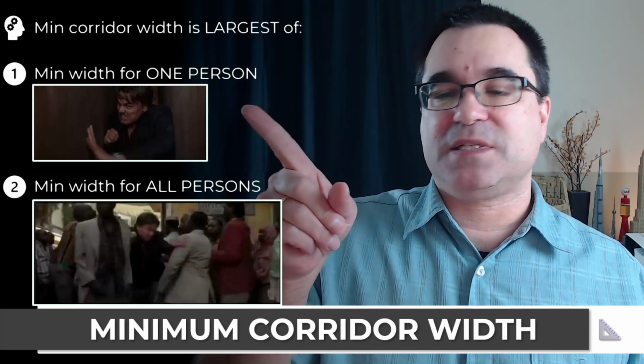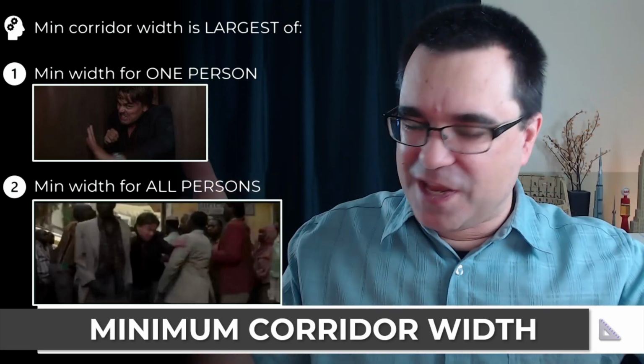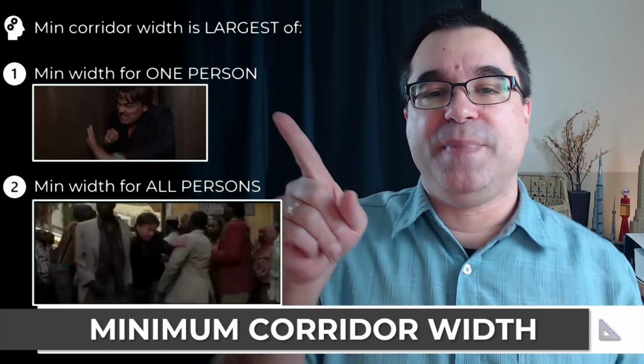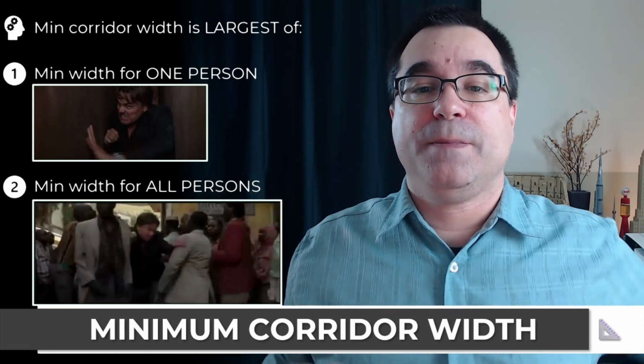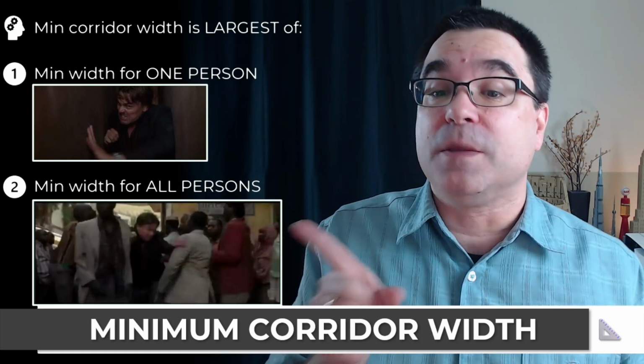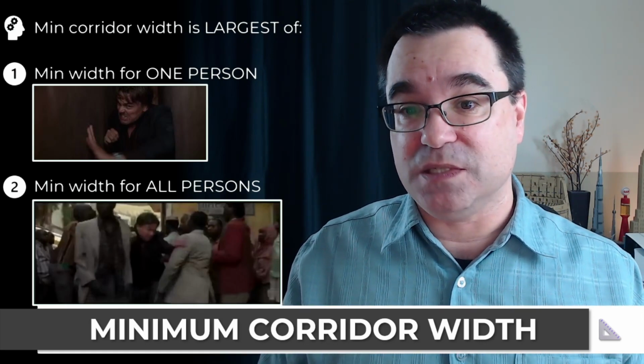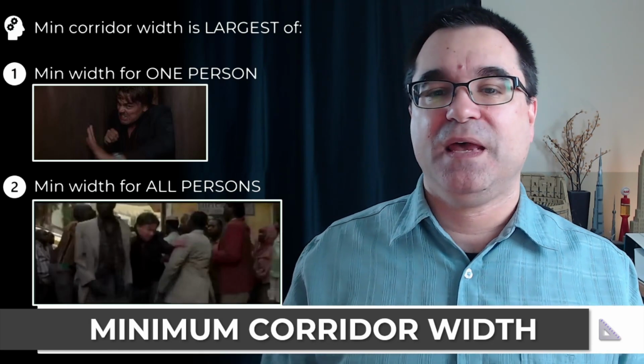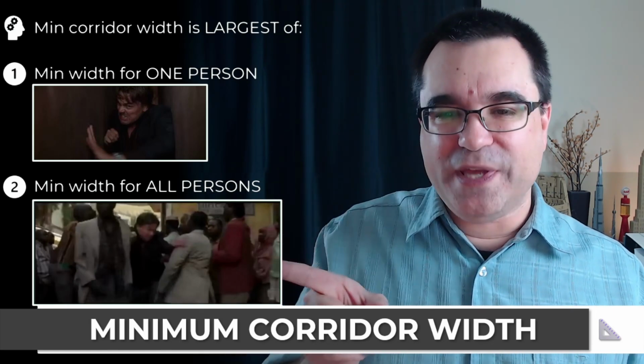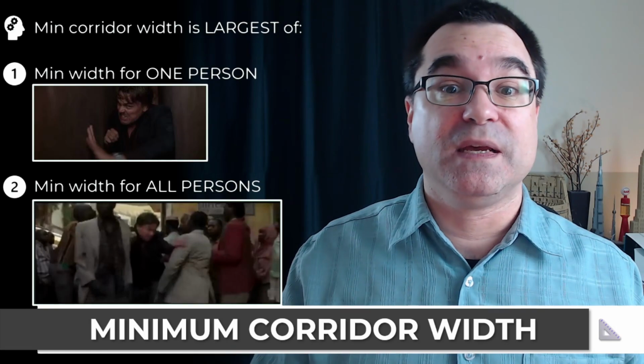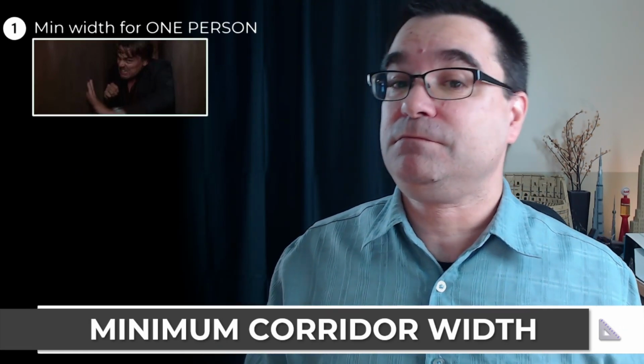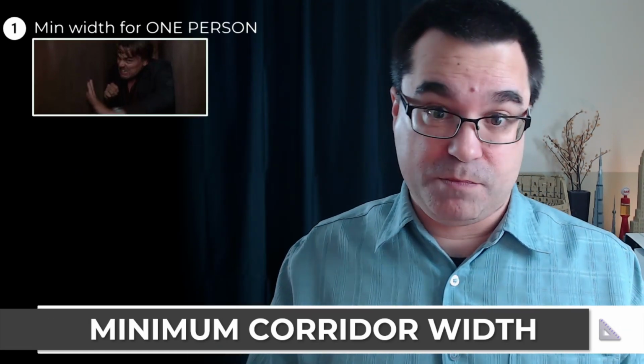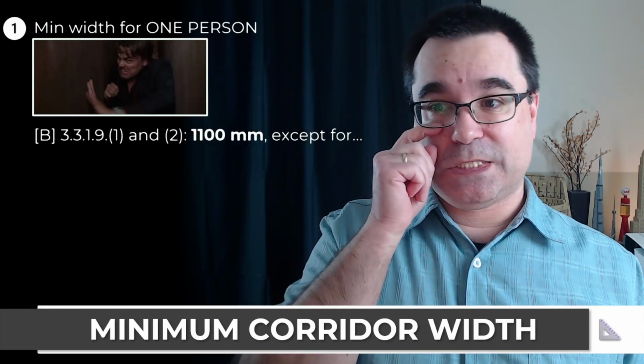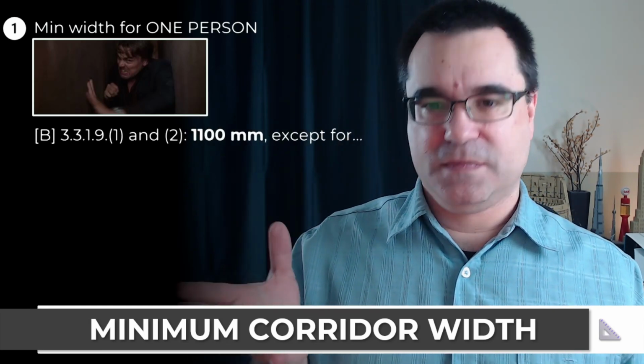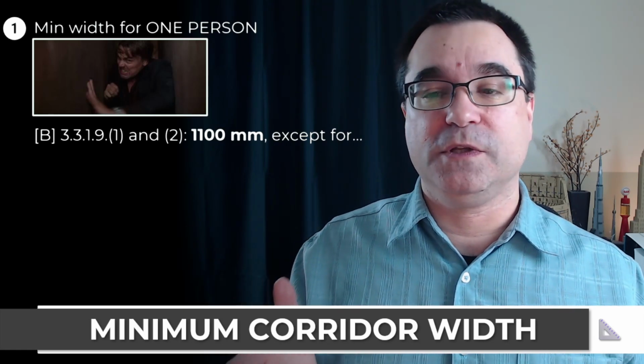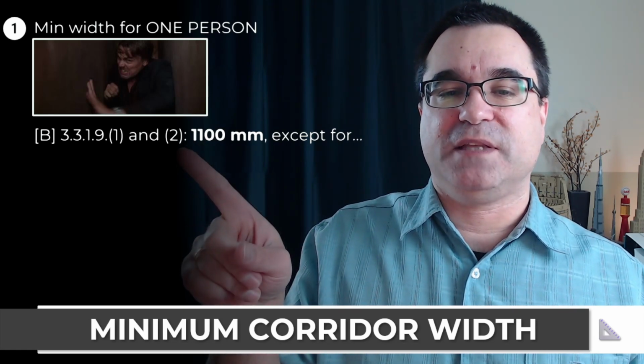So not only must that corridor or stairs or ramp or door be big enough for one person to get through, but it must also be big enough for all the people that are expected to be in that space to get through safely. You find these two widths and you always pick the larger one of the two. So let me show you how to do it for one person. Okay, you'll find this in Part 3 of the Ontario Building Code, Division B, specifically under Sentence 1 and 2.